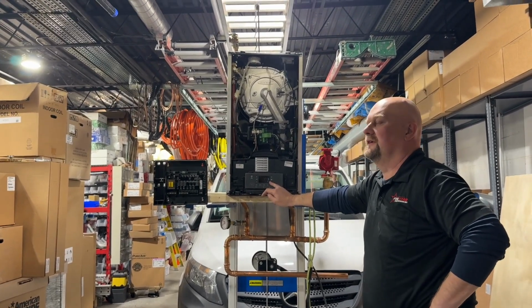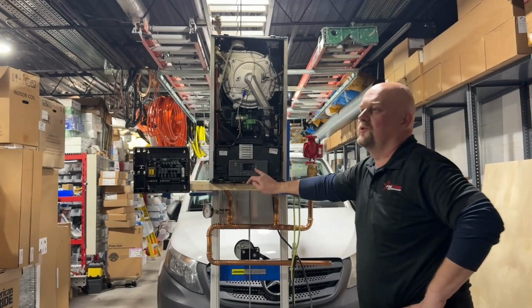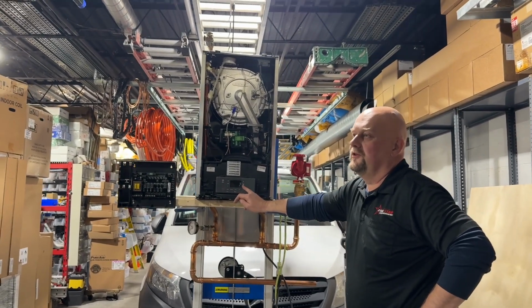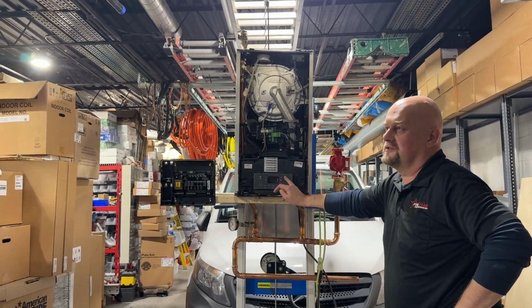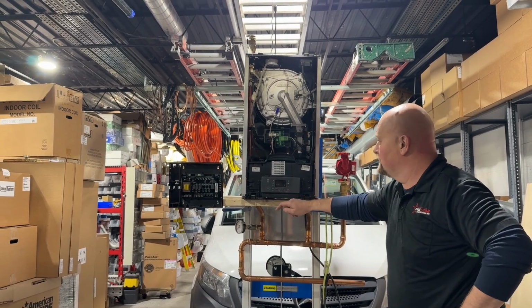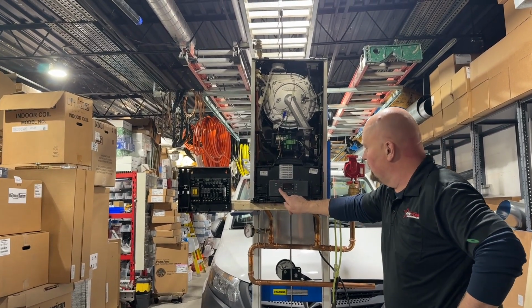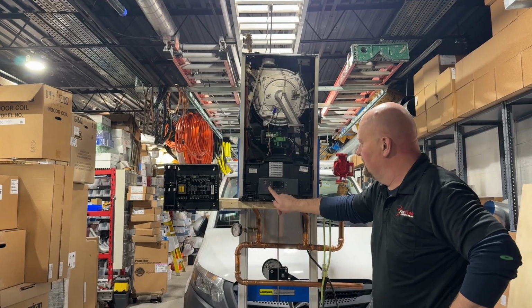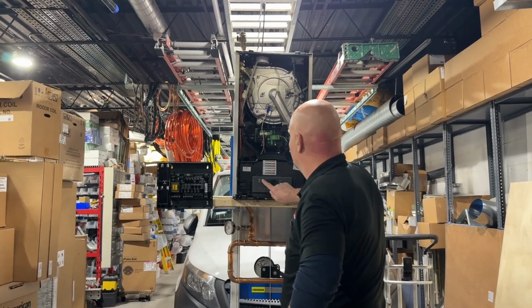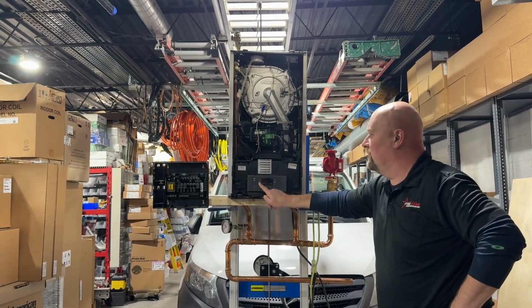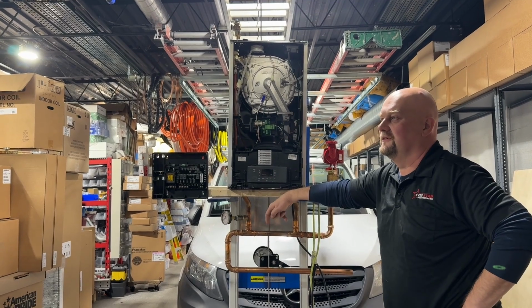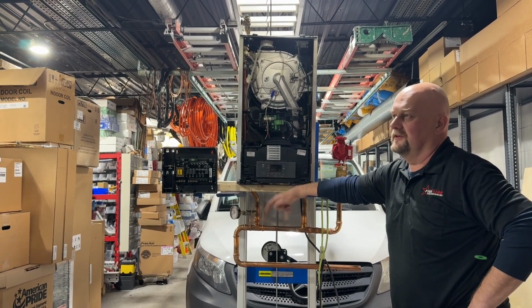If you're trying to heat up floor heated, like radiant, you want 120 degrees. If you're trying to heat up a Unico coil, 140 to 160. So remember those temperatures. And on this side, now it doesn't want to do it, but you can also change the temperature of the water that you want coming out of here too, if you're just trying to heat up a storage tank.